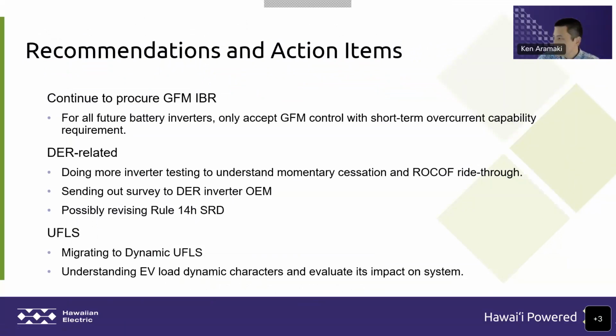Okay, so to round out this presentation, and we'll try to leave some time for Q&A, just going over a few slides with the recommendations and actions from the stability analysis. So first, we're going to continue to procure grid-forming inverter-based resources for our utility-scale resources. So for all future battery or storage inverters, only accept grid-forming control with that short-term overcurrent capability requirement that Lee went over. Right now, it's a requirement for storage inverters.